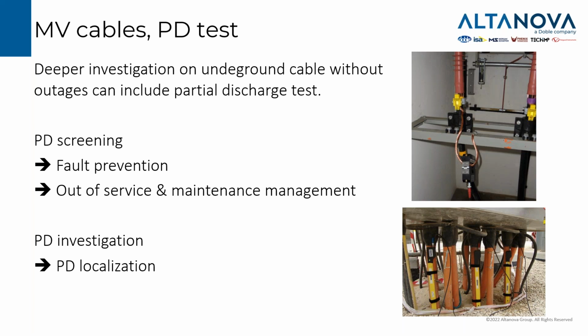You can find even more information in our previous webinars for the high voltage cable, for instance, or for medium voltage cable, where we deeply explain the partial discharge application. At this stage, we want the partial discharge to be a part or a possible solution of the strategy. So what is the difference between the survey with the RFI and thermal cameras and partial discharge? It's a more specific test because we are just investigating defects of the insulation.